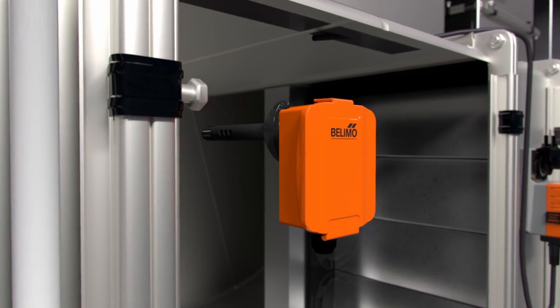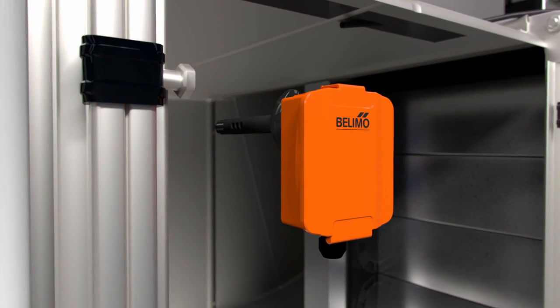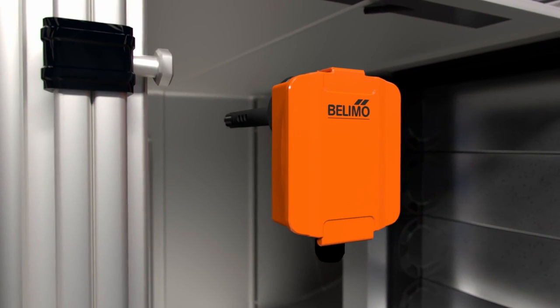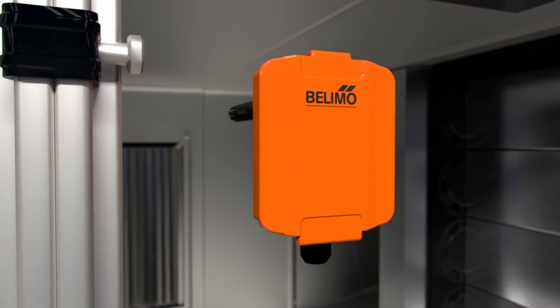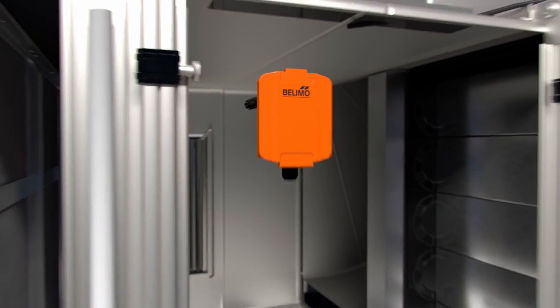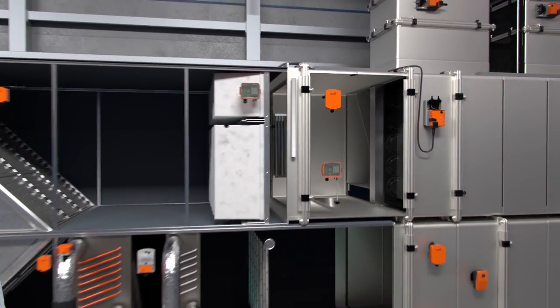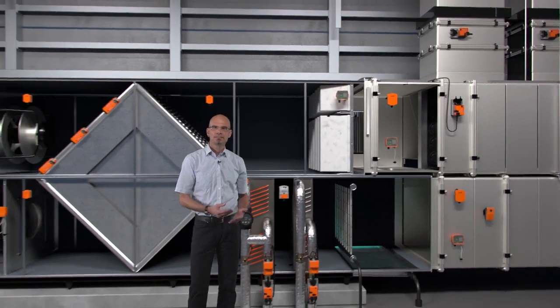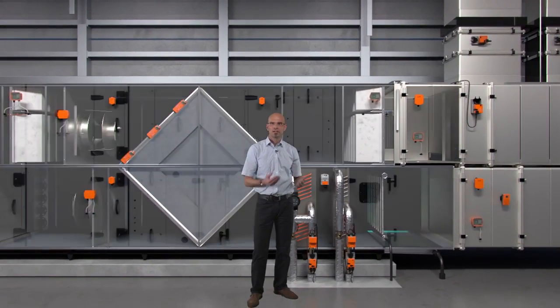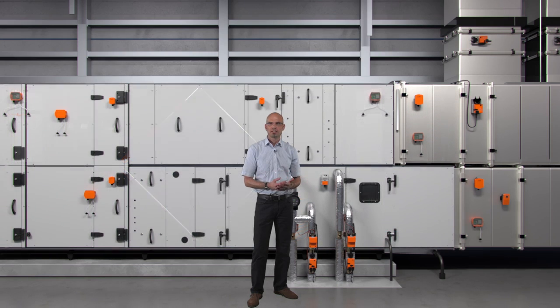Air quality sensors detect the air quality and ensure that the air handling unit can provide the amount of fresh air according to the demand in the zones and rooms. These field devices are used to control and regulate a wide variety of processes and functions inside the air handling unit. In many cases, these field devices are involved in interactions, and only in this way an air handling unit can be operated in an energy efficient manner.